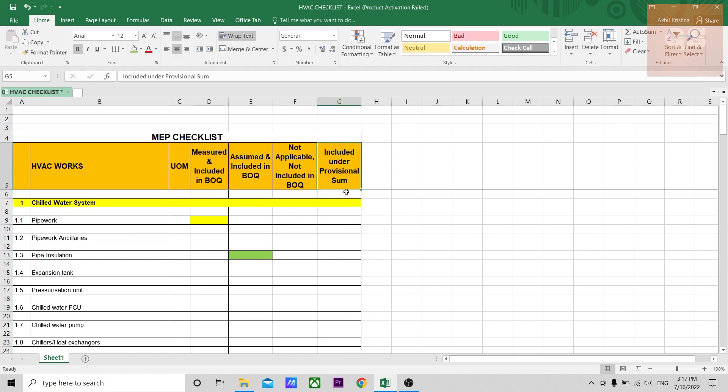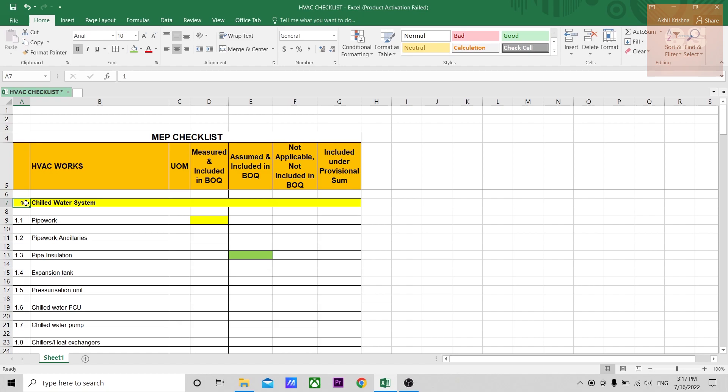Finally, there is a column for included under provisional sum. These are for items that are there in the project, but as of date or while you're doing a quantity takeoff, the design has not been developed. But later on in the execution stage or once the project begins, the design will be developed and it will be included as additional items, or accordingly a provisional sum needs to be put for these systems. Such items, for example chilled water system, the design may be in another project and the chilled water system is there but the design has not been developed, and it is mentioned that this would be put as a provisional sum. An estimate would be put during the tendering stage. For that purpose, you can hold this item and put a different color so that you'll get an idea that this system is under the provisional sum. It is there, but coming under provisional sum.